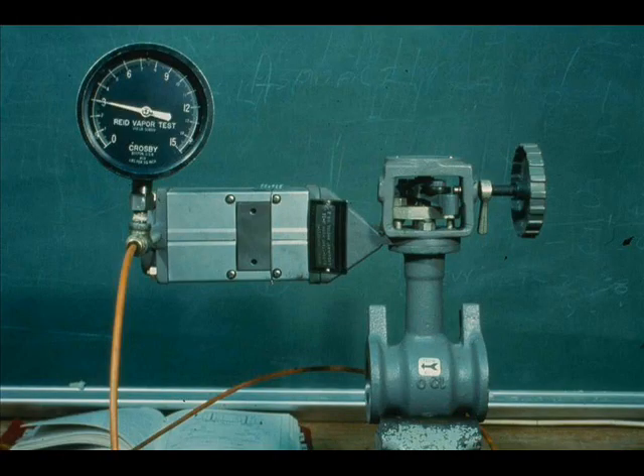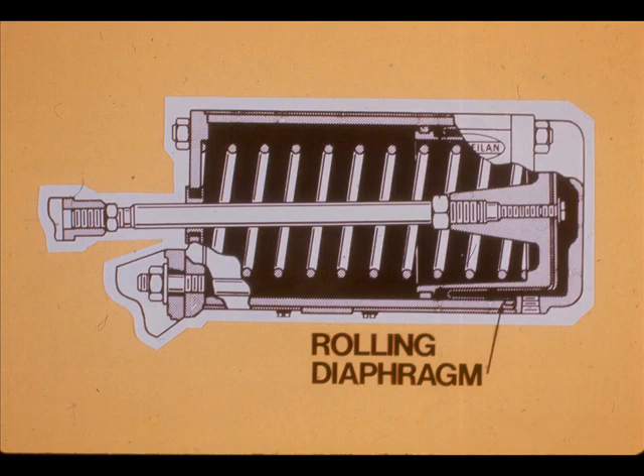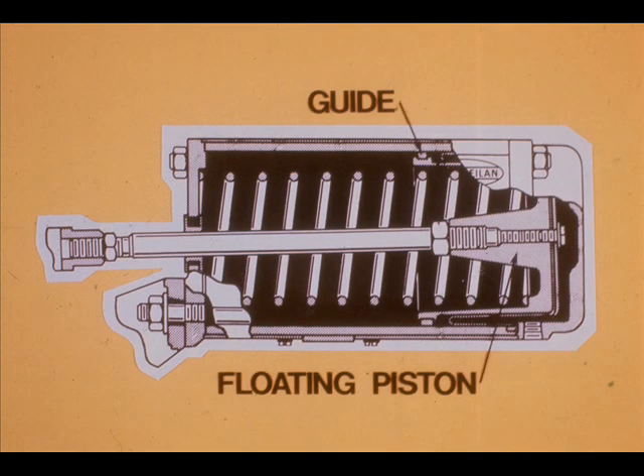The CAMFLEX actuator is a variation of the basic spring opposed diaphragm type. The CAMFLEX uses a rolling diaphragm, which permits long actuator strokes up to 7 inches. The nylon guide is not a seal — it helps align the floating piston.